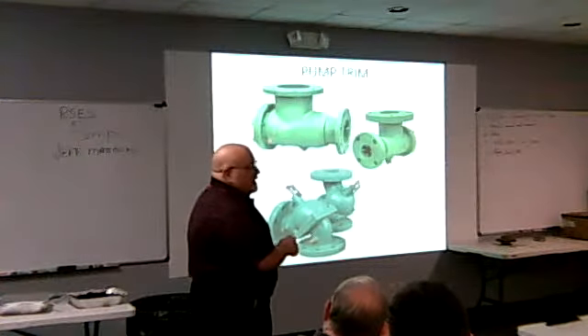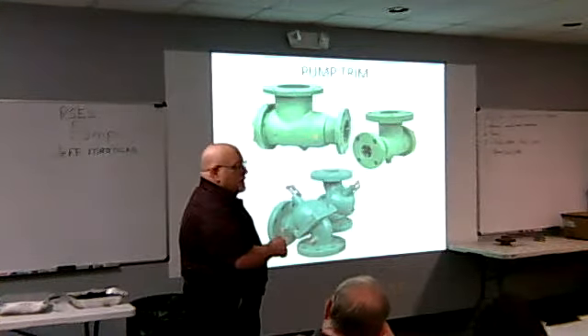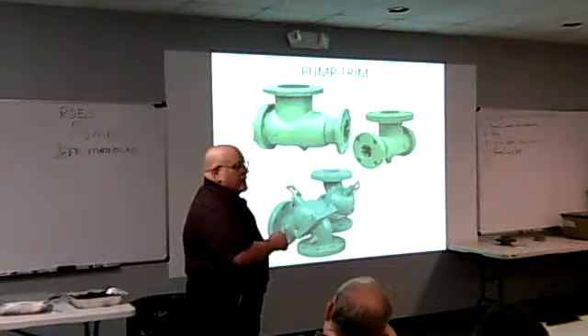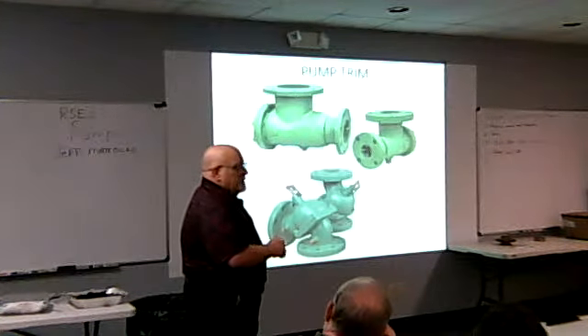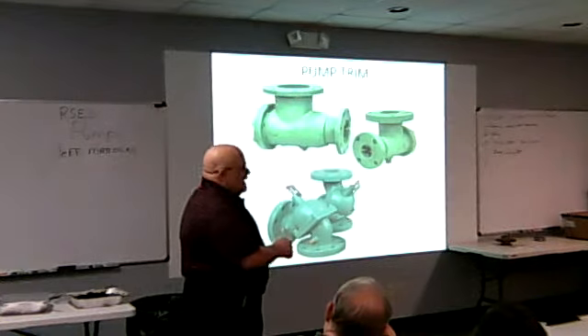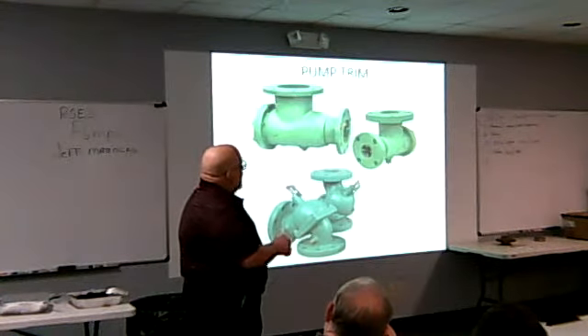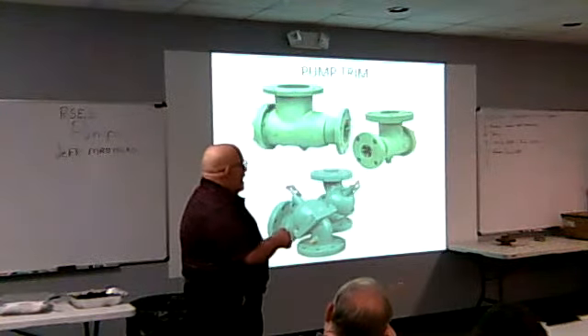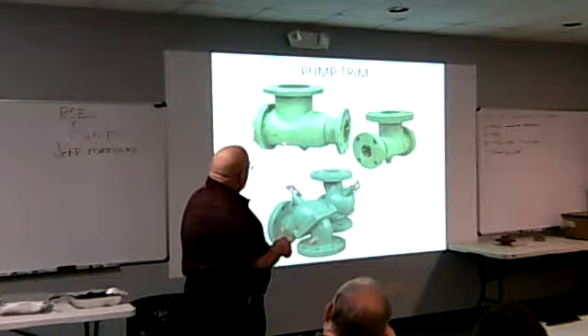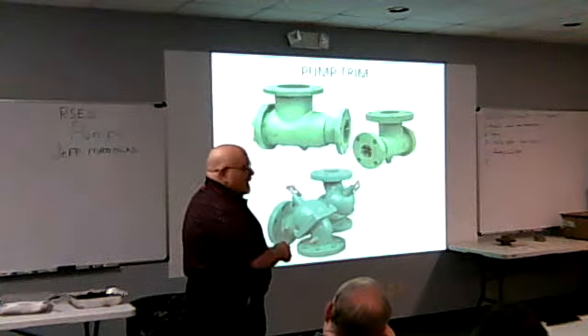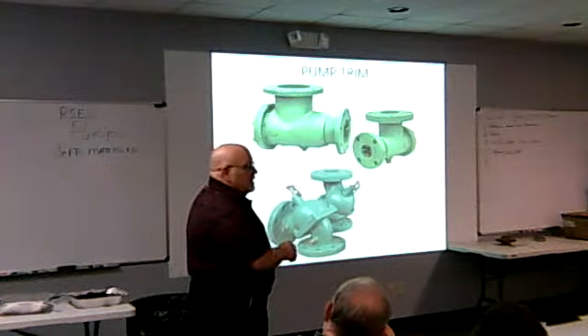There's a startup strainer in here, a 20 mesh strainer for startup. There's a 5/8 perforated strainer in here for pump protection. These give you your 90. I can reduce 6x4, 6x3. I've got my strainer. It comes with a little foot that goes on here. You put on a piece of pipe, you can jack it up for support.